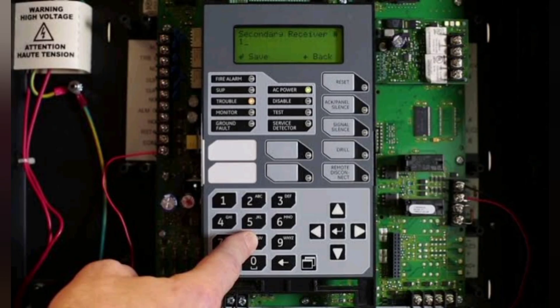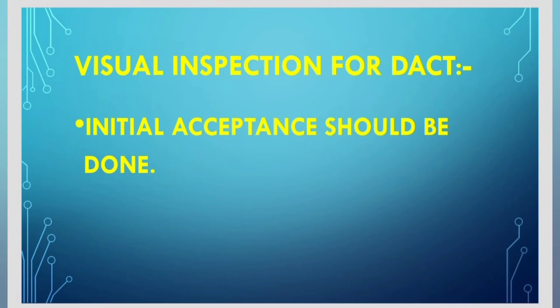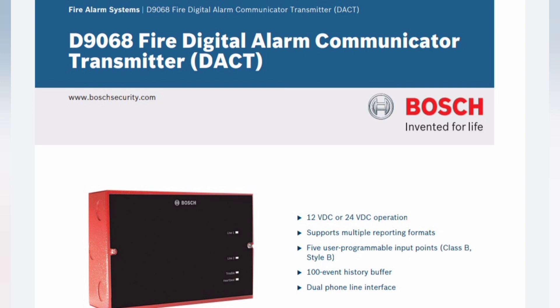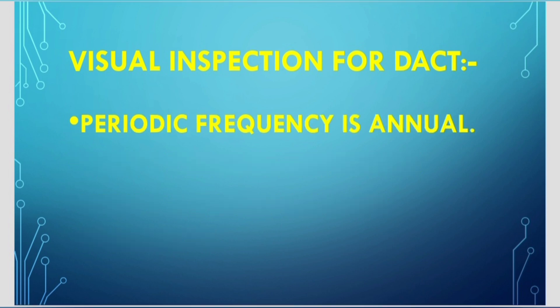Here we can discuss the visual inspection for the digital alarm communicator. For initial acceptance, the method of visual inspection requires three things as per NFPA 72: first, verify location; second, verify physical condition; third, verify system condition is normal. The periodic frequency is annual for these digital alarm communicator transmitters.